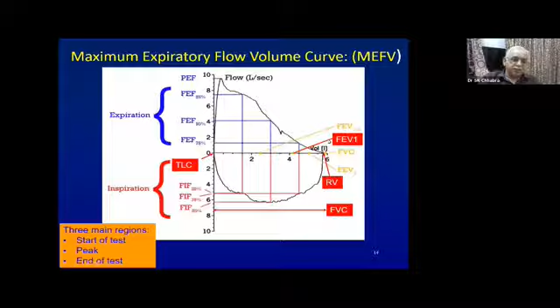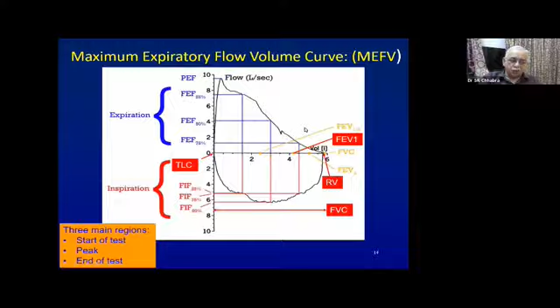Now in a flow volume curve, it is very important to remember in quality control that there are three main regions. One is the start of the test, one is the peak of the test, and one is the end of the test. When we talk of what is good spirometry, we have to make sure that the start is good, peak is good, and end is good, and there are no artifacts. Both volume-flow and volume-time graphs are complementary, and in modern machines you can get both displays from the same maneuver simultaneously in real time. The flow volume curve is more informative to pick up the correct start of the test, the peak, and the middle part for artifacts.